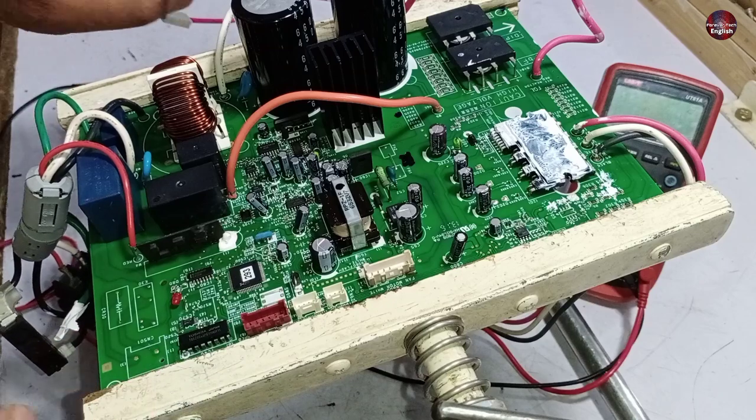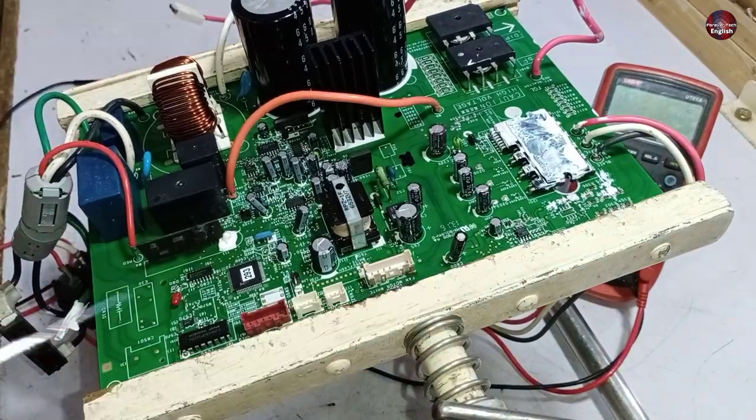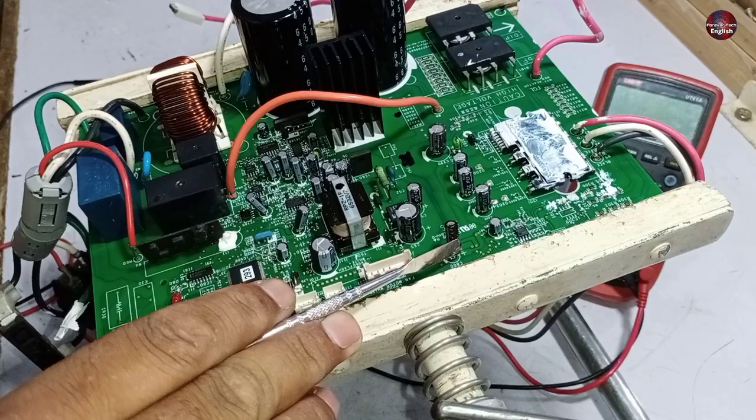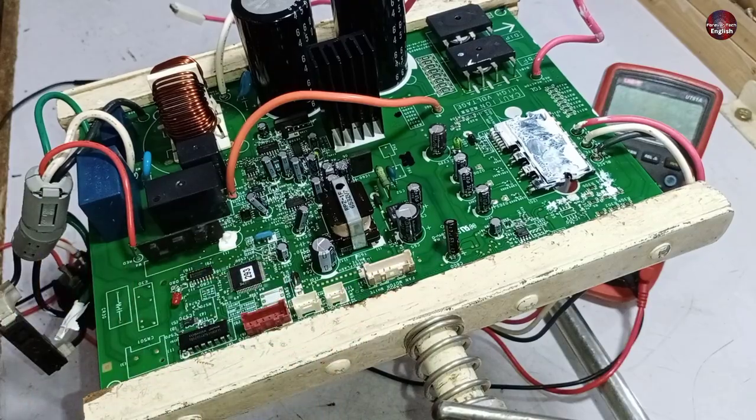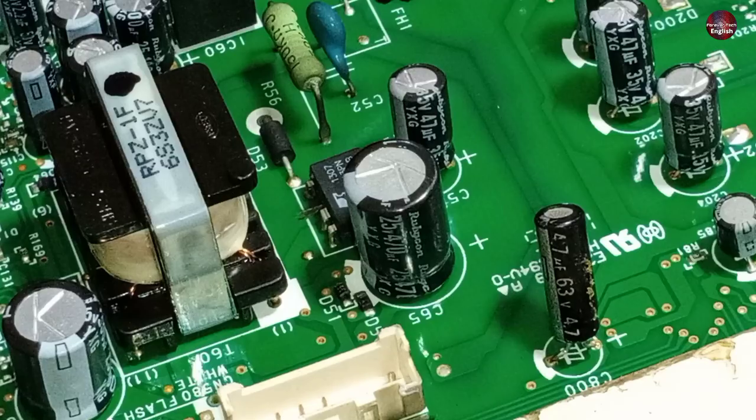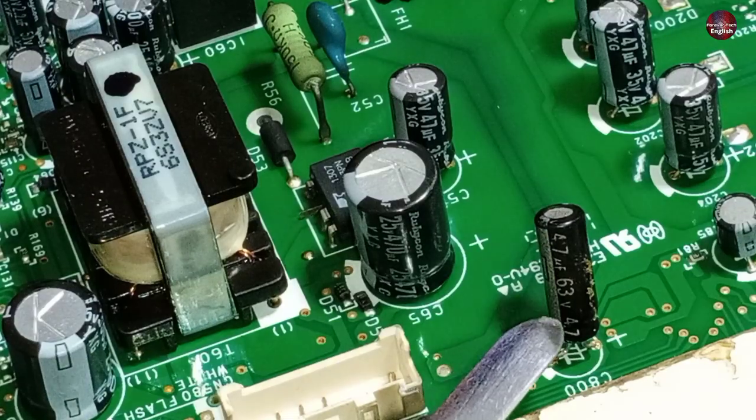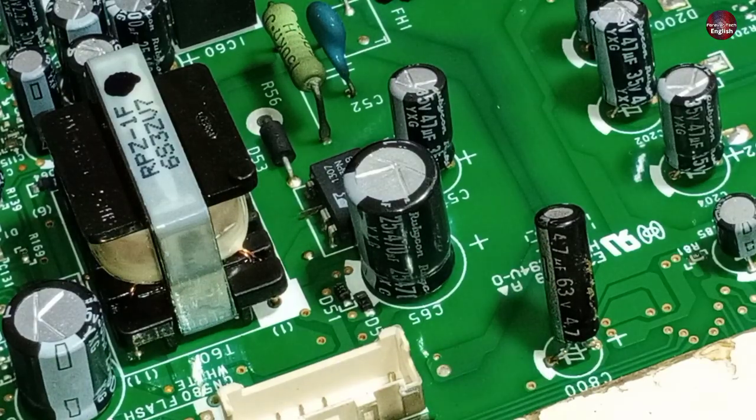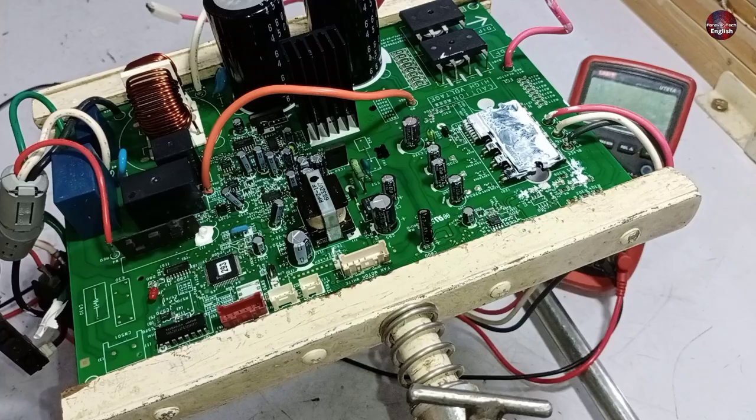The problem was with the control voltages of the control board. So I have changed this capacitor. Let me zoom in. As you know, I have replaced the capacitor with 4.7 microfarads and 63 volts, but before, the capacitor contained 50 volts.